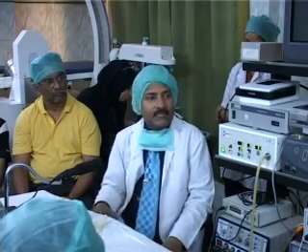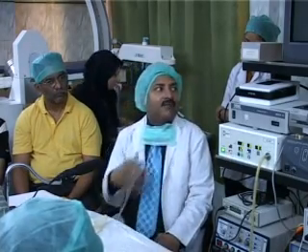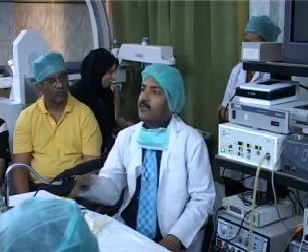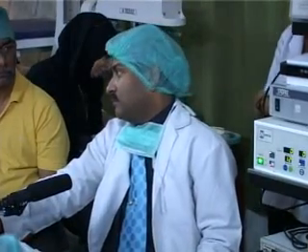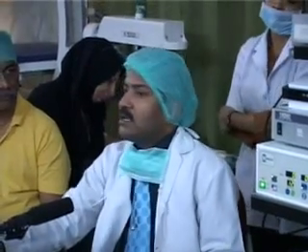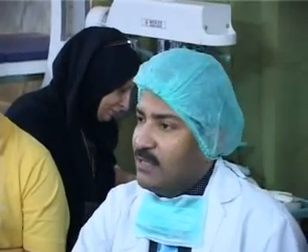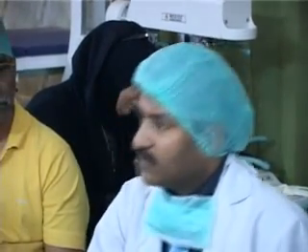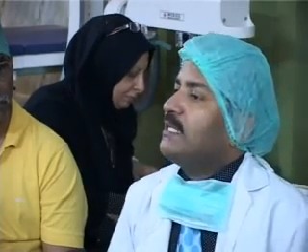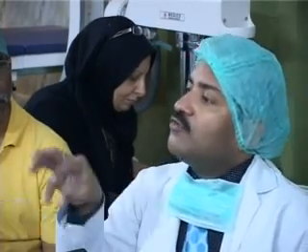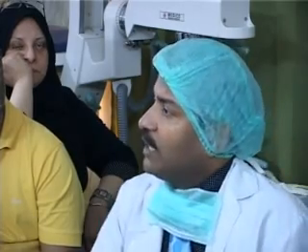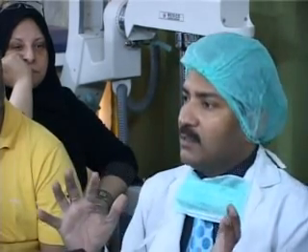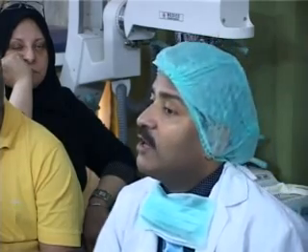But if the patient is under general anesthesia, there will be no shivering; the patient will have myocardial depression, and then there will be ventricular arrhythmia, and after that there may be ventricular fibrillation. So you must be concerned about excessive leak. If excessive leak is there, this is one consequence. To stop that, many companies started using a CO2 warmer. The insufflator has an inbuilt CO2 warmer. The good thing is that it will keep the CO2 warm, so that hypothermia will not develop.